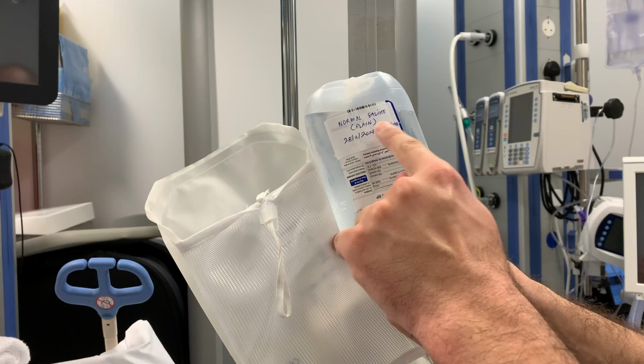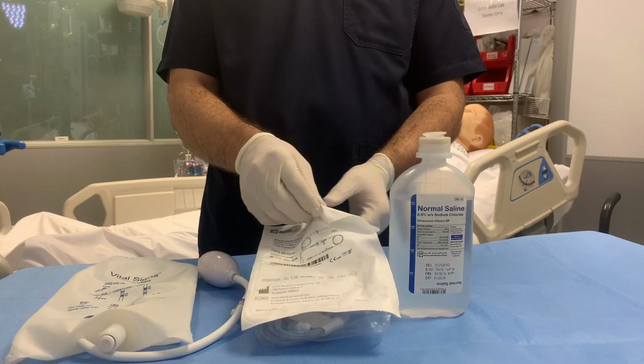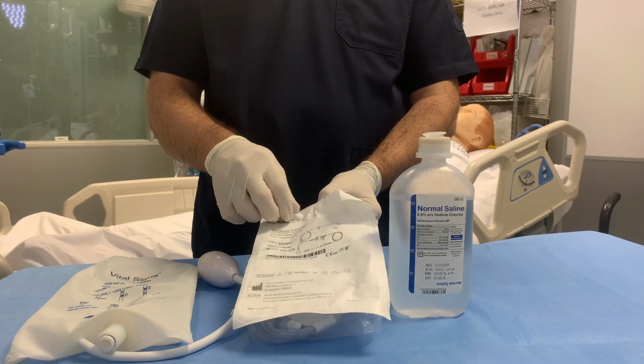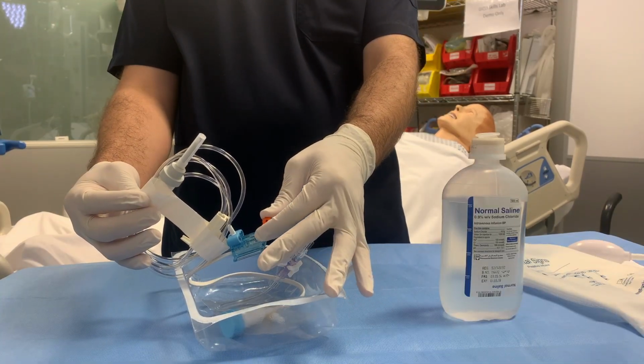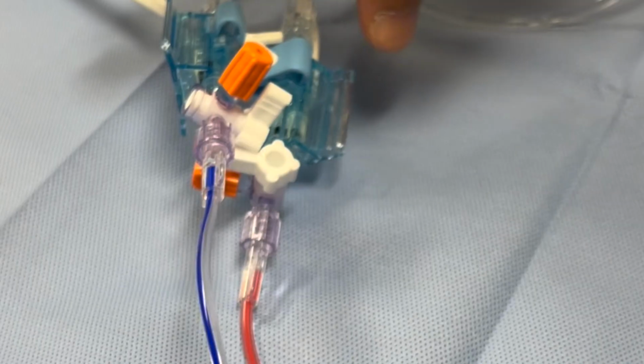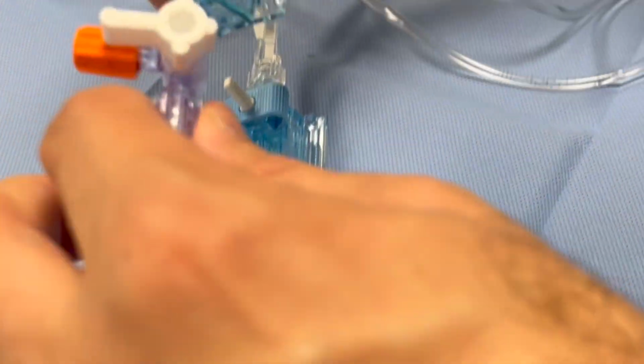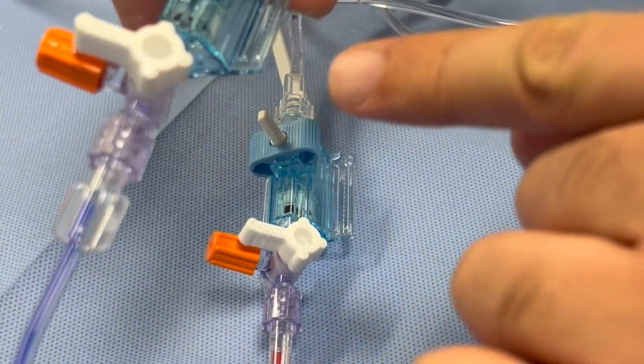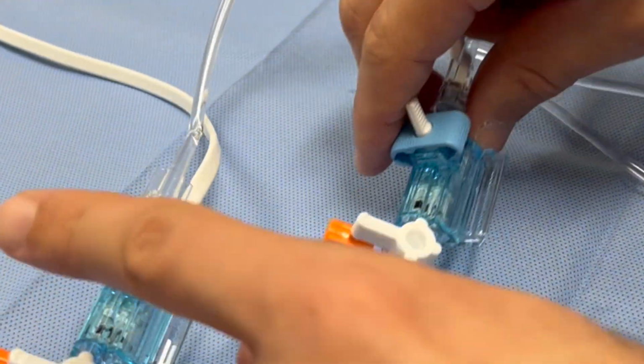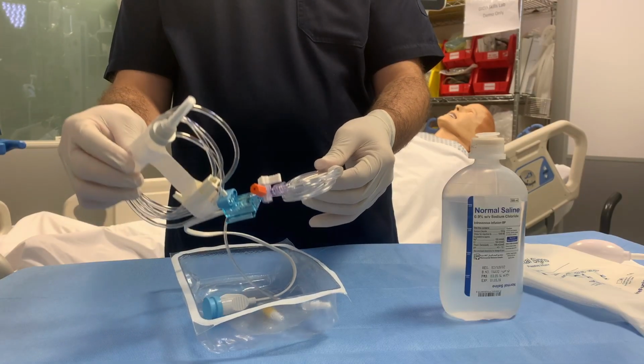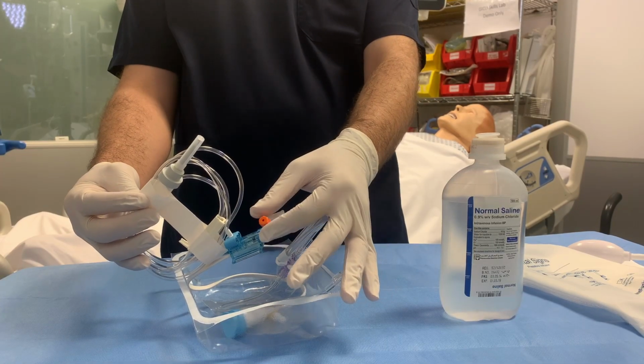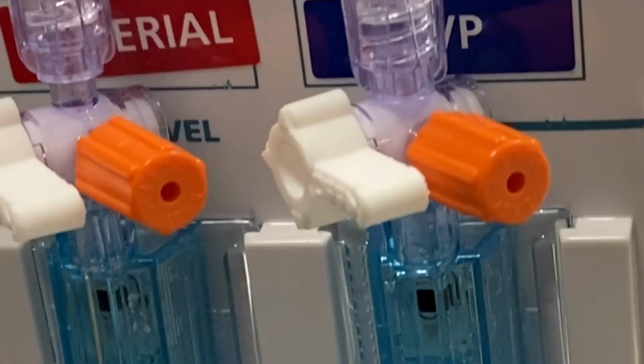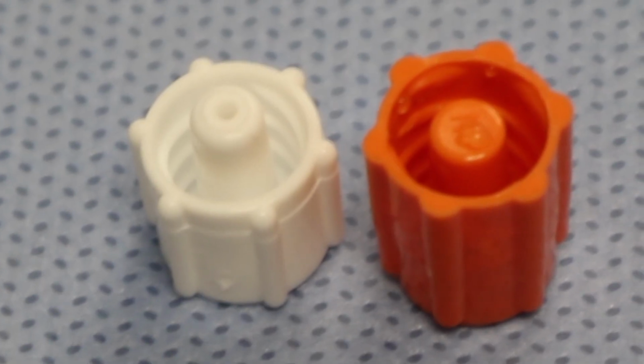Now prepare the system. Open the packaged pressure transducer kit with aseptic technique. Tightening the connections prevents air from entering the system and fluid leaks. In this system, I did not find any need for more tightening because it's already tightened. As a standard, you need to change the vent cap, remove it, and replace it with a new sterile one. In this system, no need to change the caps, as per the manufacturer's recommendations.